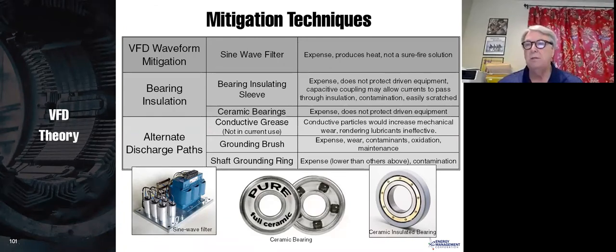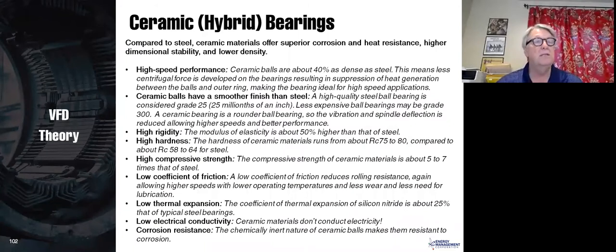We have largely moved away from these because if you have even a little scratch in there, then that doesn't work, and you can still get capacitive currents through there. So we really prefer a pure full ceramic bearing. In these cases, the bearing balls are actually ceramic. They're not steel. And these work fantastically well. They also last probably 10 times as long as a standard bearing.